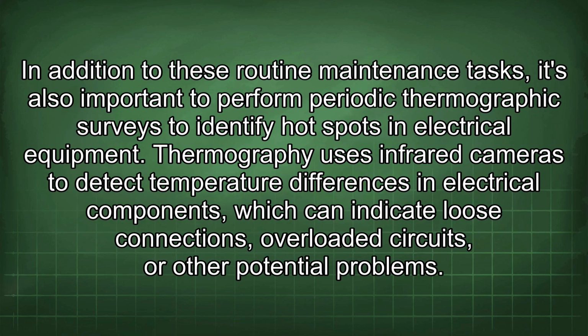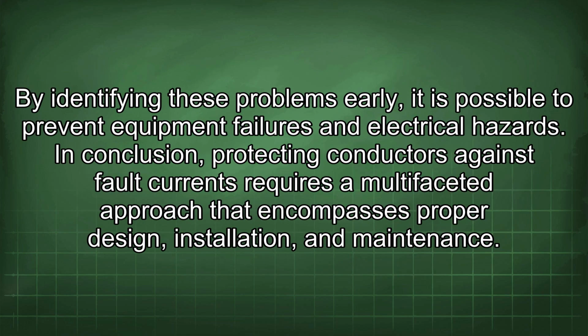In addition to these routine maintenance tasks, it's also important to perform periodic thermographic surveys to identify hot spots in electrical equipment. Thermography uses infrared cameras to detect temperature differences in electrical components, which can indicate loose connections, overloaded circuits, or other potential problems. By identifying these problems early, it is possible to prevent equipment failures and electrical hazards.